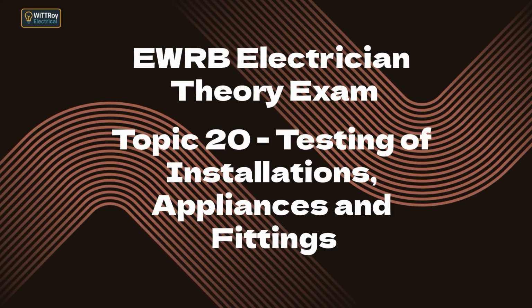Topic 20c. Explain the specific tests that are required by AS/NZS 3000 and state the test instrument type required to perform each of those tests. AS/NZS 3000 and AS/NZS 3017 specify the full set of mandatory tests. 1. Continuity of earthing conductors. Instrument: continuity tester or multifunction tester. 2. Continuity of protective bonding. Instrument: continuity tester.